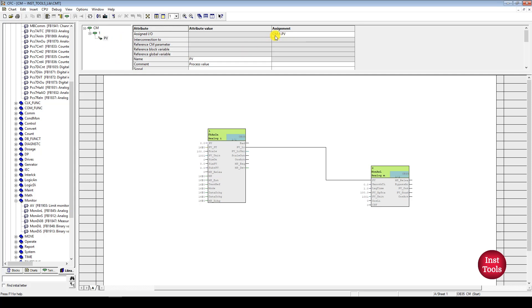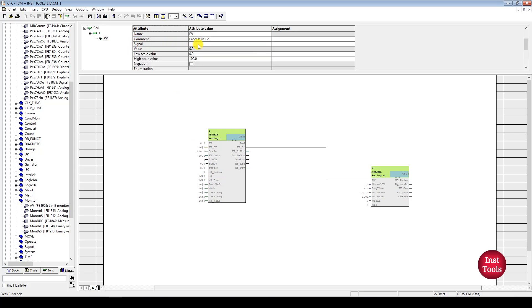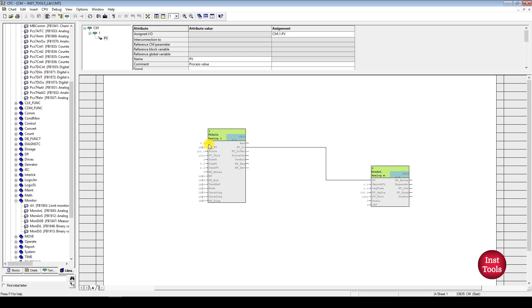We are connecting internal parameters of CMD to the outside world — this is the gate. The PV signal is connected to CM1 PV as an assignment. So whenever connecting to a hardware signal, it is directly connected to this assignment, which is the PV variable. When connecting pins internally between two FB blocks inside one CMD, there is no requirement to add those pins to the TED level.